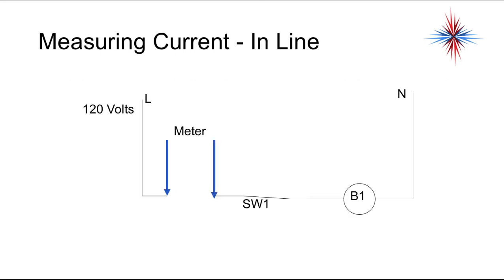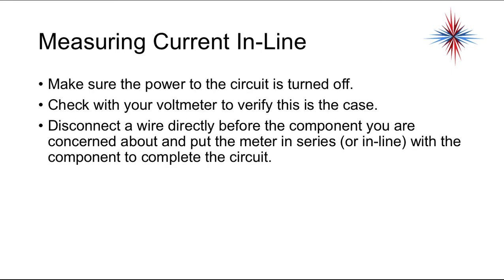To measure current in line, put your meter in series with the circuit. In other words, you have to make a break in the circuit, put one meter lead on one side and one meter lead on the other side. Again, be very careful on amperage on this one because you can damage your meter. Make sure the power to the circuit is turned off. Check with your voltmeter to verify this is the case.